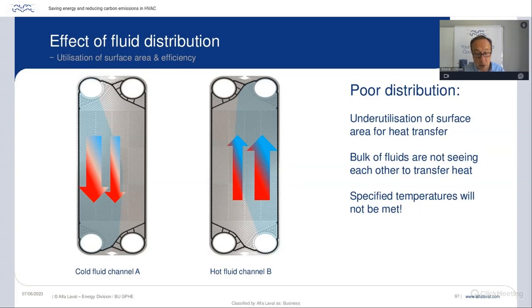Most likely there will be fouling, and that's going to mean that you have to open and clean the heat exchanger, or the fouling is going to increase your pump pressure and pumping costs even more. So to sum up, Alfa Laval does have a lot of features, and for all these features, the end user should not pay more than 10% over a competitor's heat exchanger. And what these features do is provide excellent distribution through the channel, which ensures that the Alfa Laval heat exchanger stays clean longer. So that would be the summary of, you know, going into the kitchen of plate heat exchanger design and operation.